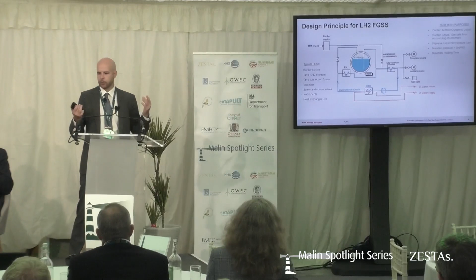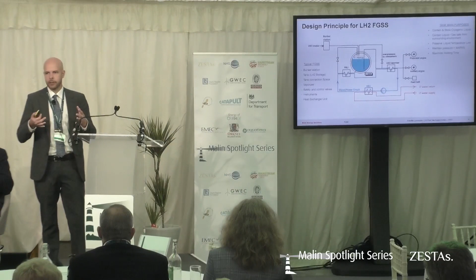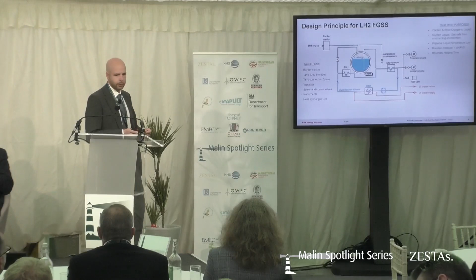So the main purposes of this system are to contain and store cryogenic liquid hydrogen, to contain the liquid and gas safe from surrounding environments. We don't want any gas leaks where it's not supposed to be. It's supposed to preserve the liquid temperature low, maintain pressure below the max allowable relief valve setting, and to maximize your holding time. The holding time is basically all the time you can keep liquid hydrogen in these tanks without needing to vent off in order to release anything through your safety relief valves. So this is done with vacuum technology.